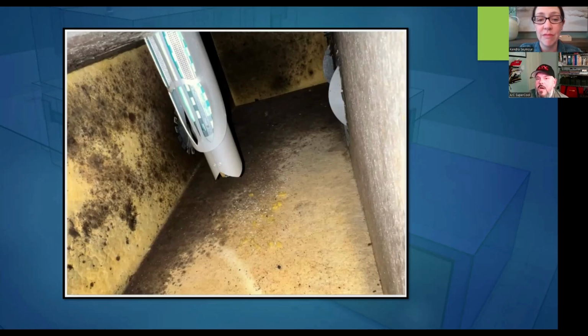Filtration—you have to have effective filtration to stop the junk from getting in there to begin with. Effective filtration is not a one-inch filter in the grill. It's a media filter designed for the system, as close to the system as possible, and it has to be tight with no bypass. All the air going through that system, I want it to go through that filter.